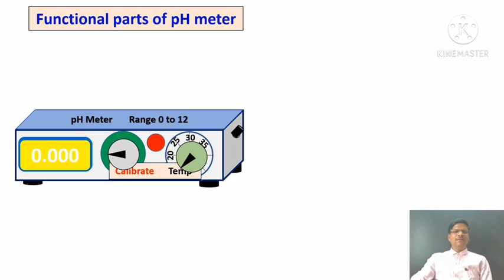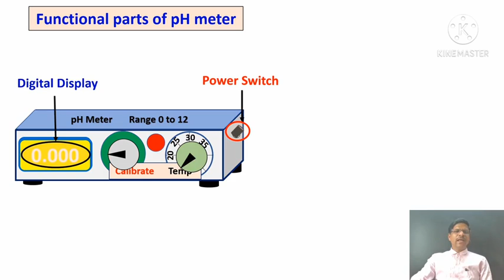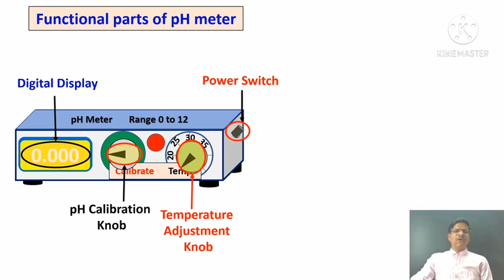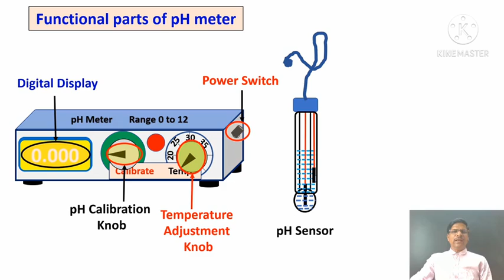If you see the pH meter, it is an electronic device, and the functional parts of any pH meter are the power switch, digital display, temperature adjustment knob, and pH calibration knob. These are the functional parts of any pH meter. The most important functional part of the pH meter is the pH sensor or H+ ion sensitive electrode. It is also called a combined glass electrode. Now we will explain the pH sensor.